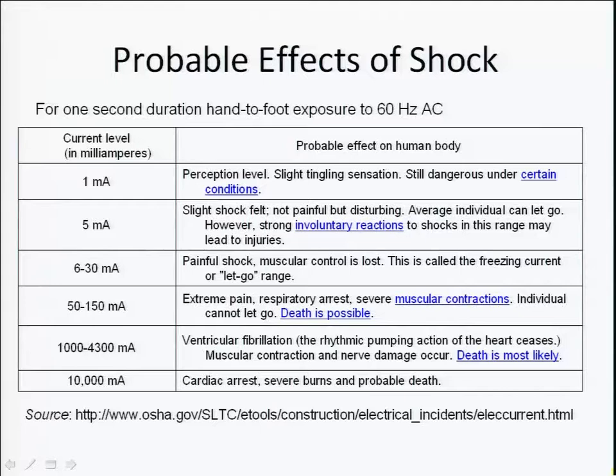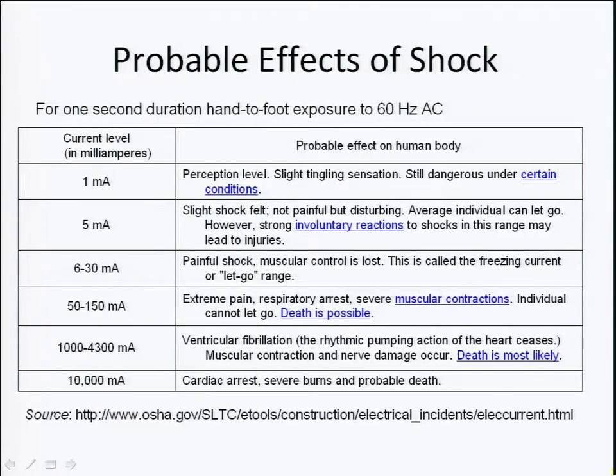In the 6 to 30 milliamp range, the shock can be painful and muscular control is lost — this is called the freezing current or let-go range — where you completely lose muscular control and can't drop things. This range also carries the same dangers noted for the 1 and 5 milliamp ranges and can be extremely dangerous to people with certain medical conditions.